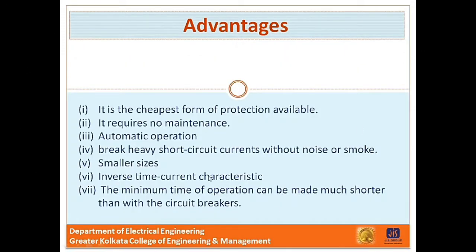What are the advantages of using a fuse? First, it is the cheapest form of protection available. It requires no maintenance. Its operation is inherently completely automatic, unlike a circuit breaker which requires elaborate equipment for automatic action. It can break heavy short circuit currents without noise or smoke. The smaller size of a fuse imposes a current-limiting effect under short circuit conditions. The inverse time characteristics make it suitable for overcurrent protection. And the minimum time of operation can be made much shorter than with a circuit breaker.